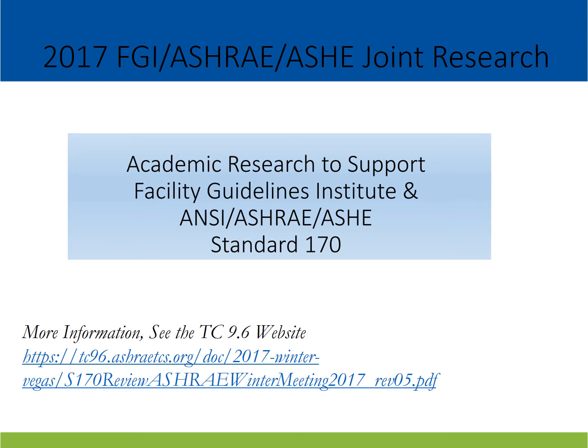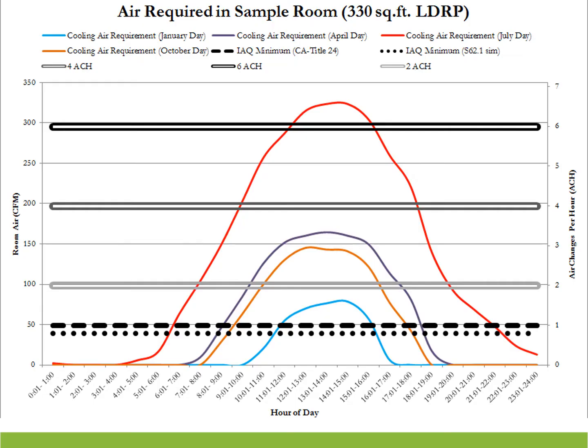But if you want to place bets, I will stay after the meeting, and I'm taking bets. My bet is most of the requirements in 170 are circular, and they don't really have an origin. We've been repeating them for years and years and years, since about the 1960s, and we're not really going to find any evidence behind them, right? In particular, nobody's getting any benefit from those total air changes per hour where we're over-ventilating all of our non-critical spaces. And we are over-ventilating. Here's a good example.